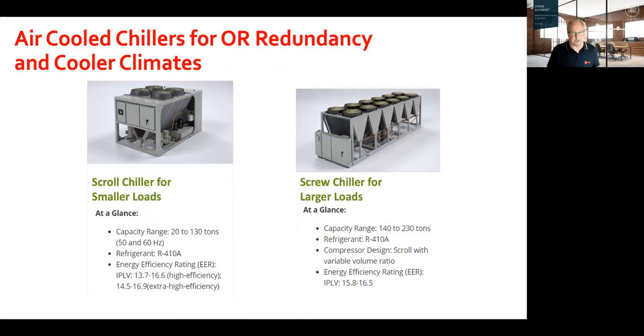Speaking again to redundancy, a little blip on the air-cooled chillers. Again, I'm from Michigan, so we typically drain our chillers right after the first holiday in November. That is the opening day of white-tailed deer hunting. So we do that after all the techs get back from deer hunting and before Thanksgiving. That's not to say we don't get a 60-degree day in the wintertime.